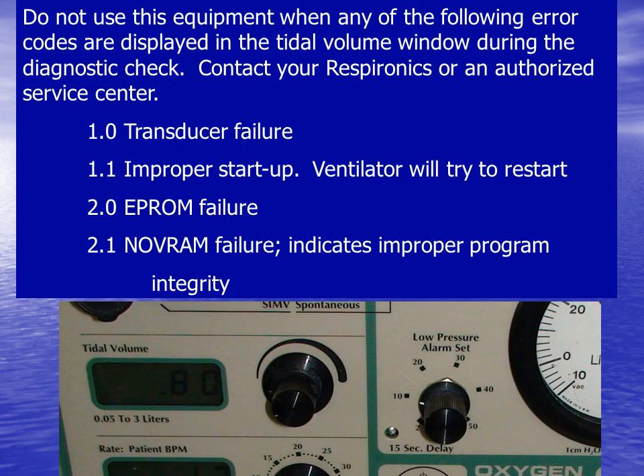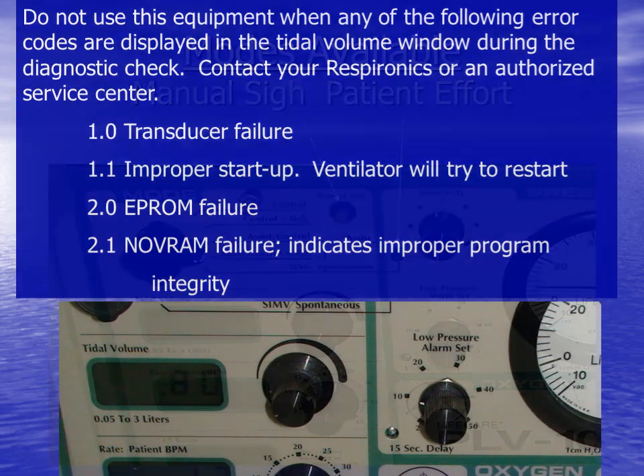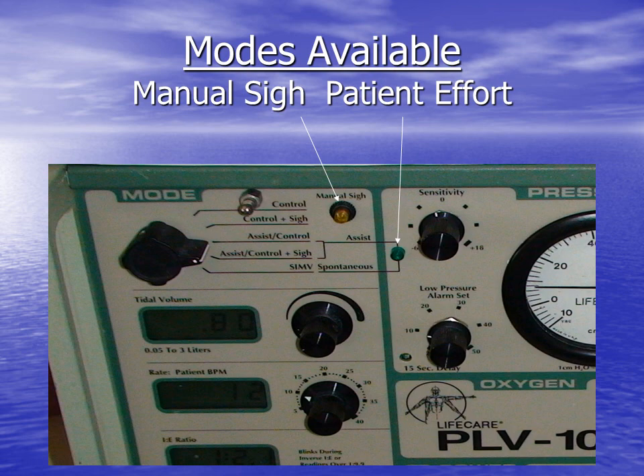When the vent is first turned on, it powers up and automatically runs a diagnostic check on itself. If any of the above codes are displayed in the Tidal volume display window, do not use the ventilator. The PLV 102 offers control and assist control modes, as well as both of these with the addition of a Sigh function. It offers tidal volumes from 50 cc's to 3 liters. It also offers an SIMV mode with rates from 2 to 40 breaths per minute. This vent can provide inspiratory flow rates of up to 120 liters per minute. The green LED next to the modes lights up to indicate patient effort.